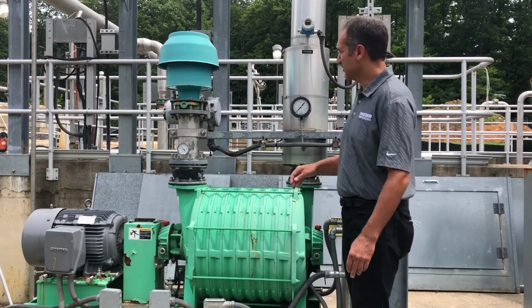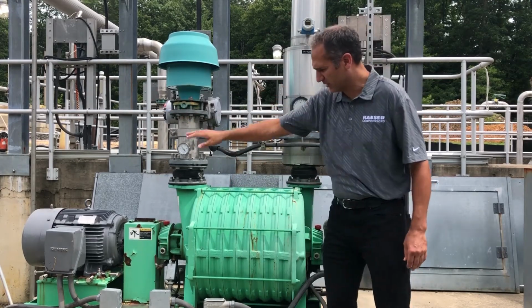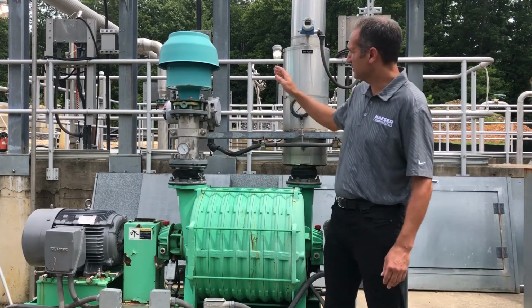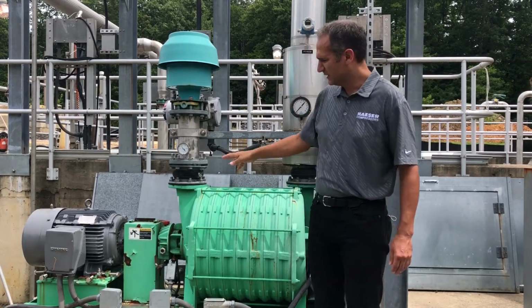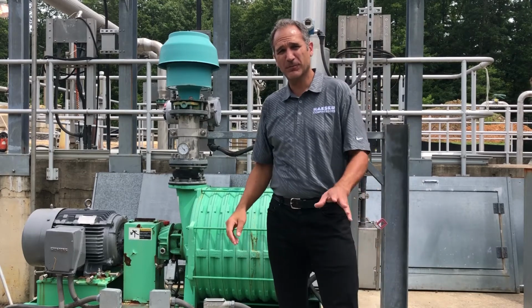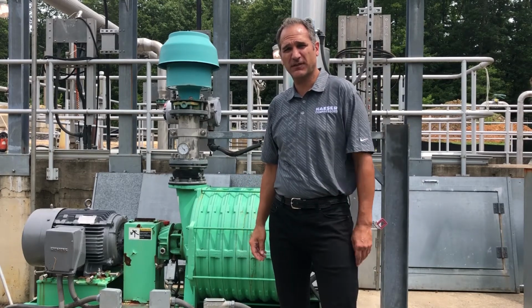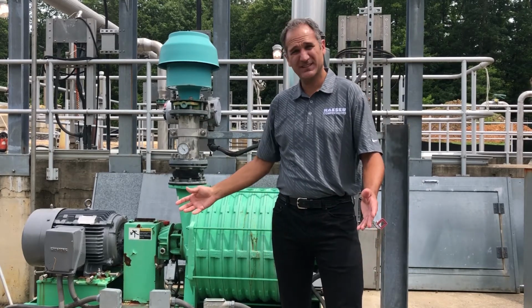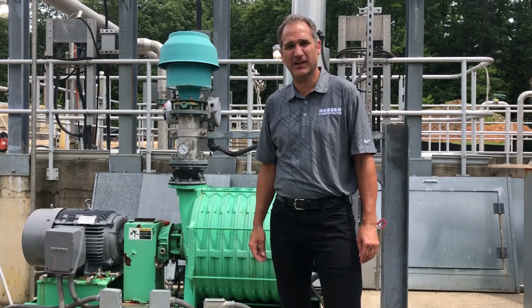With that, we can essentially account for all these items included in the system, all the losses to the filter, on the discharge, the coupling, and get a true performance of the machine rather than a theoretical one. Again, this process is known as an ADA, an Air Demand Analysis.